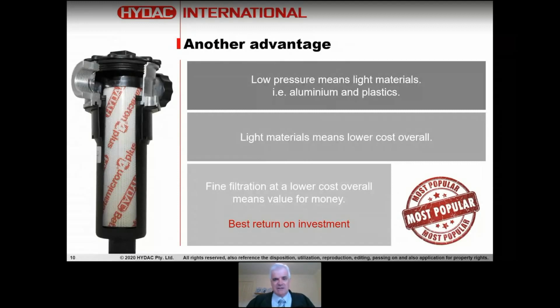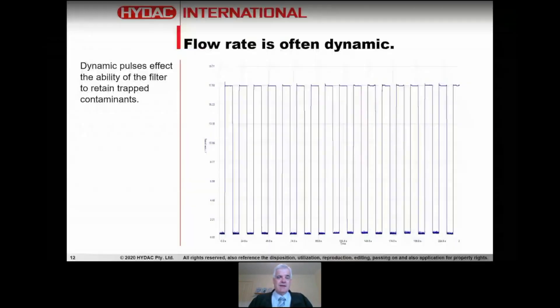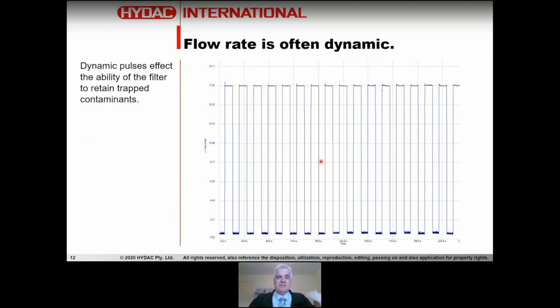There are some disadvantages. One important consideration is that in the return line you can get a changing flow rate all the time. For example, a reading of an actual return line showed flow going from basically zero to 18 liters a minute - on, off, on, off. Dynamic pulses will affect the ability of the filter to retain trapped contaminants. For that reason alone, return filters may not be enough to ensure your cleanliness target is met - you may have to use other forms of filtration such as offline filtration.